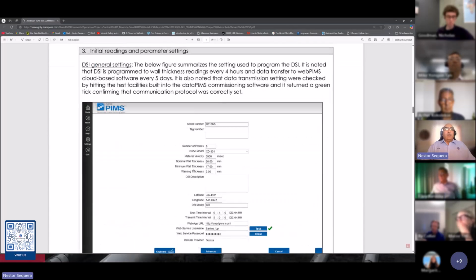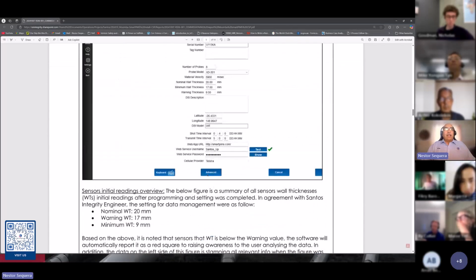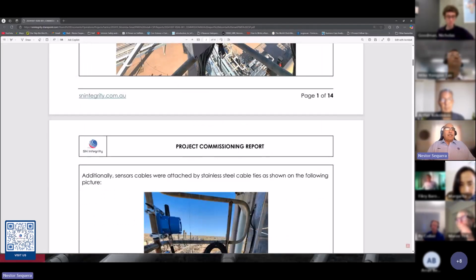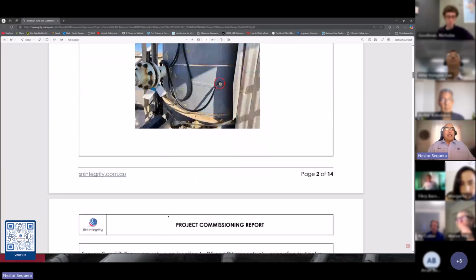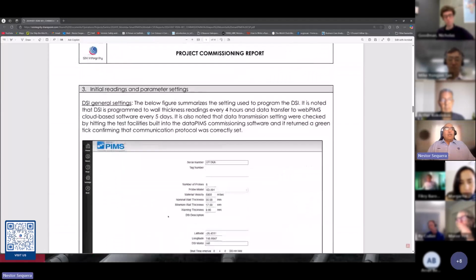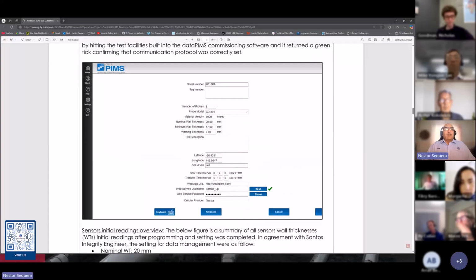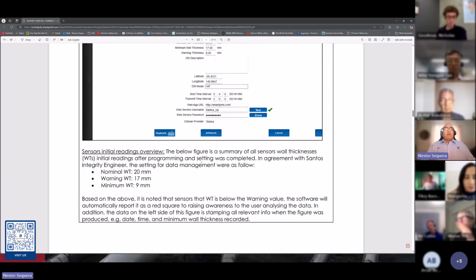When we are commissioning, we connect it to the DSI, which is the blue box on the picture. This box here, we can connect a laptop to it and program it. So we document all that data that we use. So for instance, the shot interval of UT values is every 4 hours. The transmit interval is every 5 hours. At the time, we also do a test of data transfer to the cloud and confirm that it is okay. Then we program the sensor in agreement with the client.